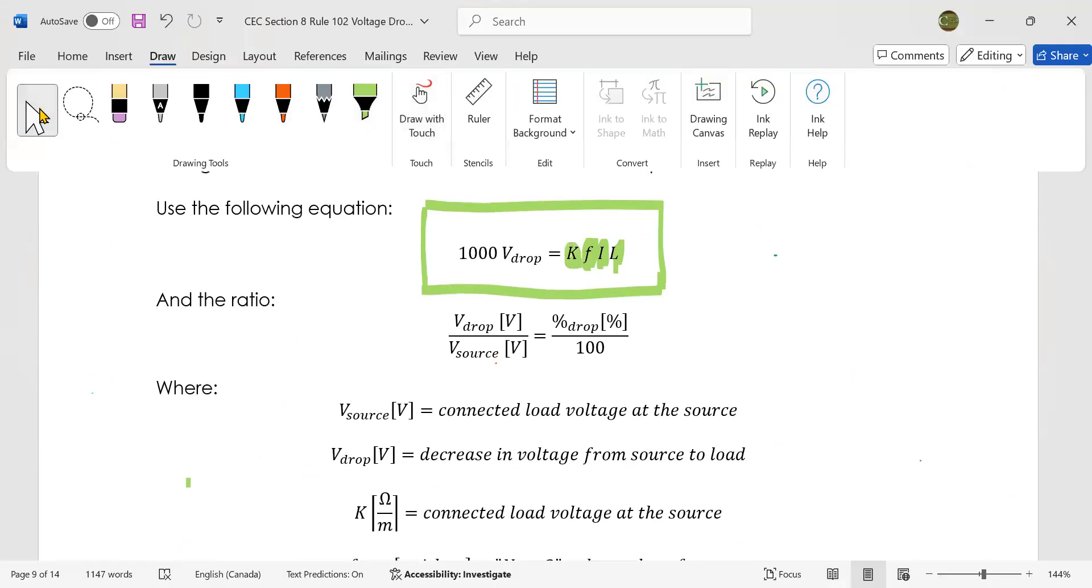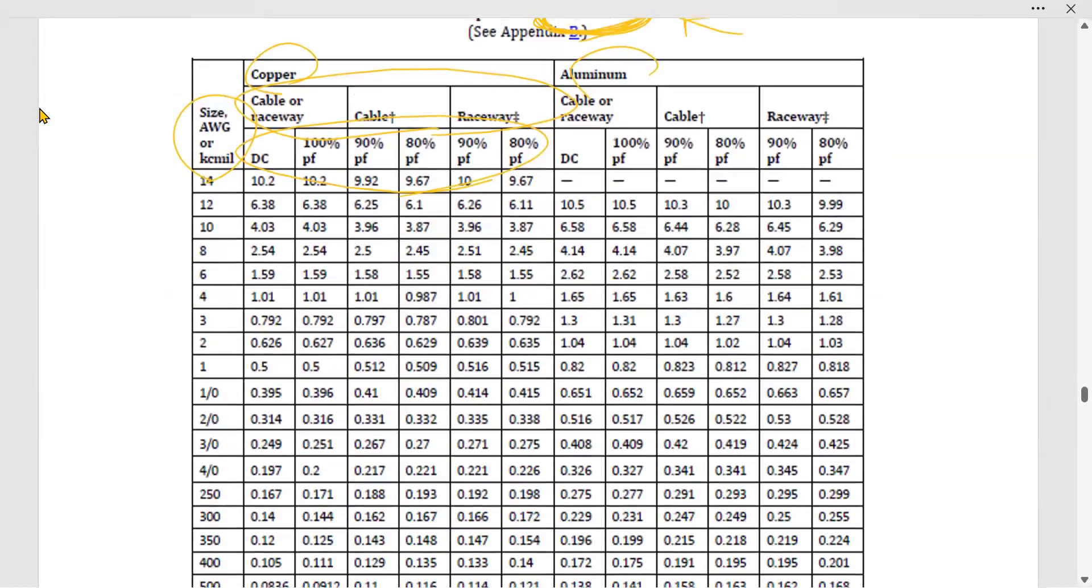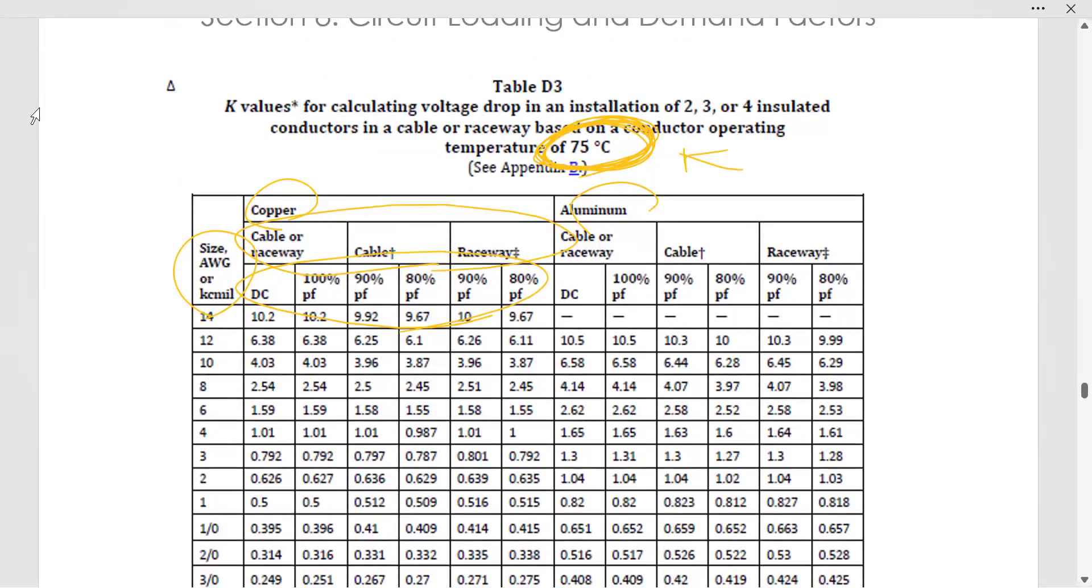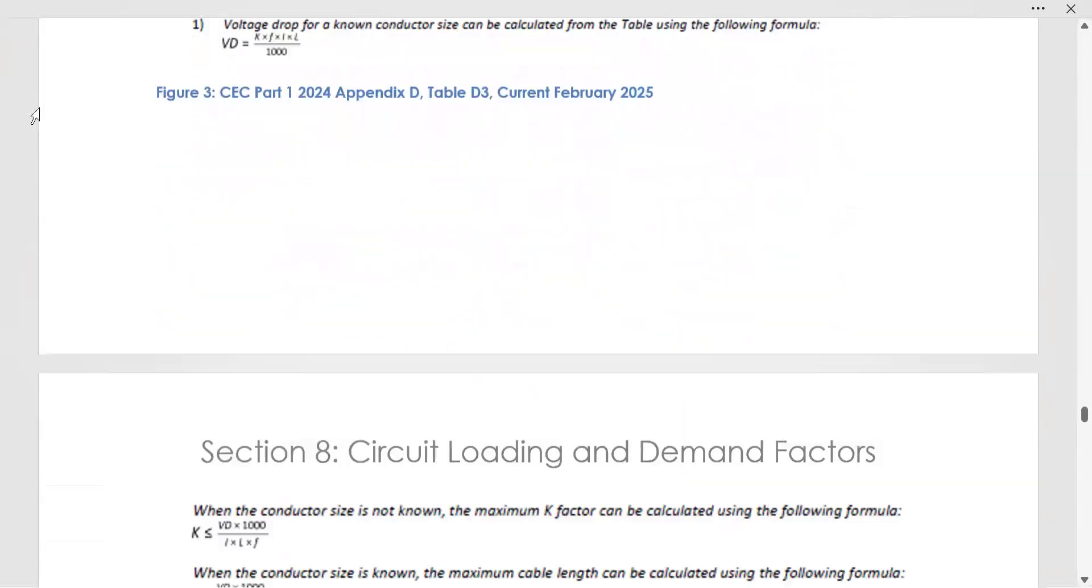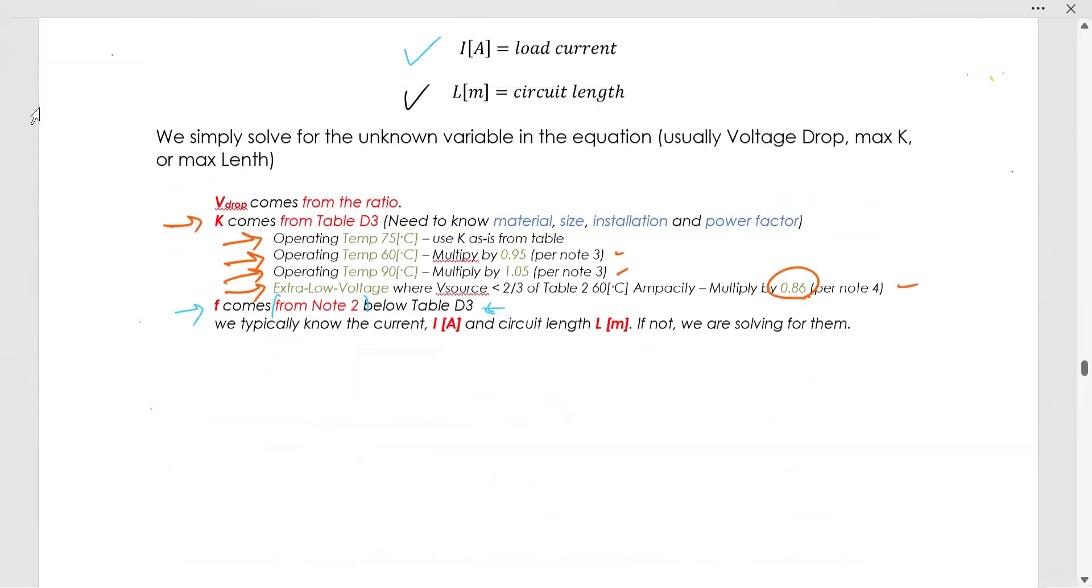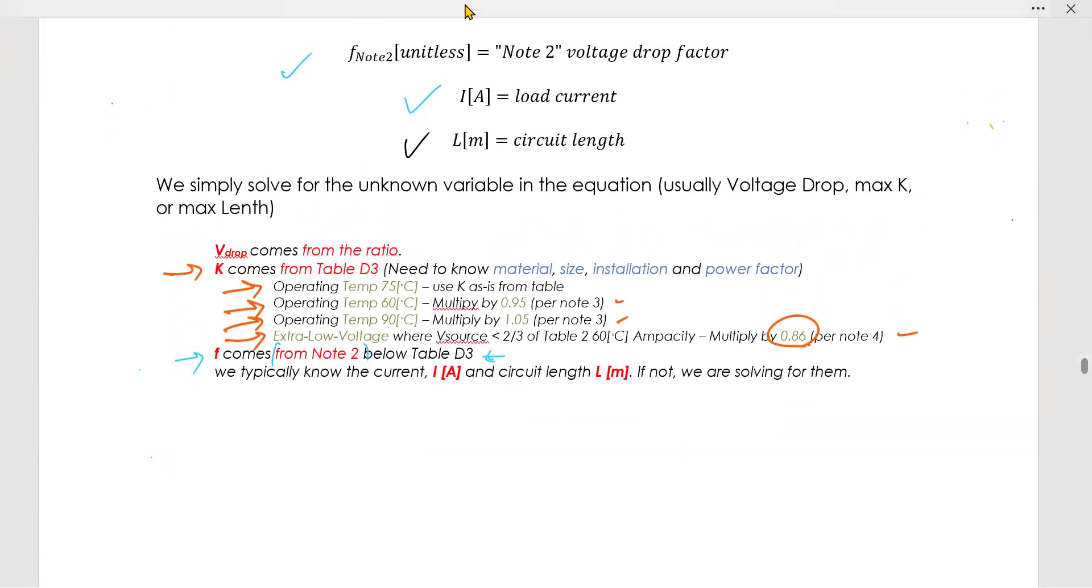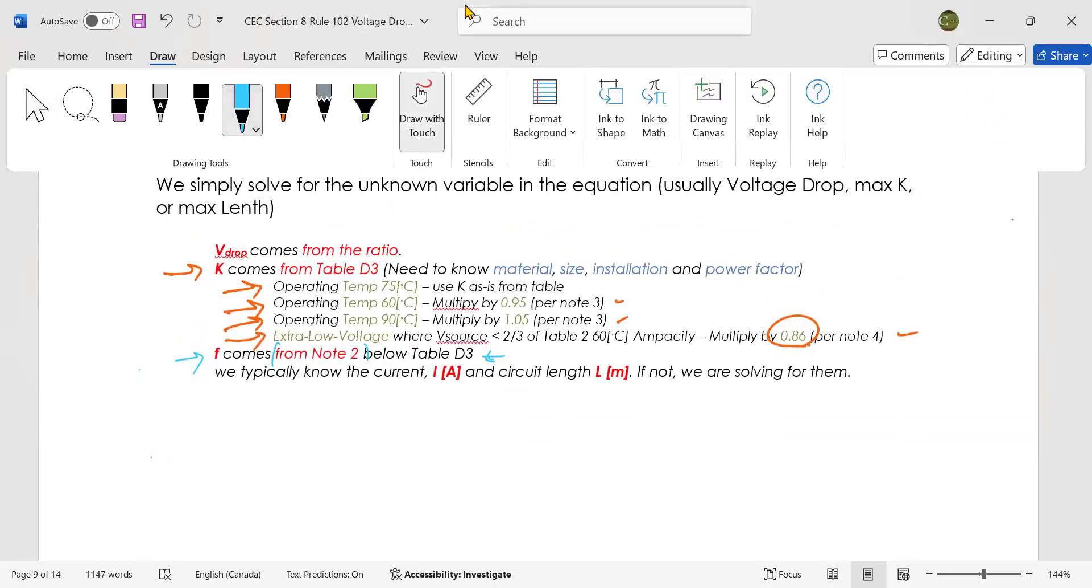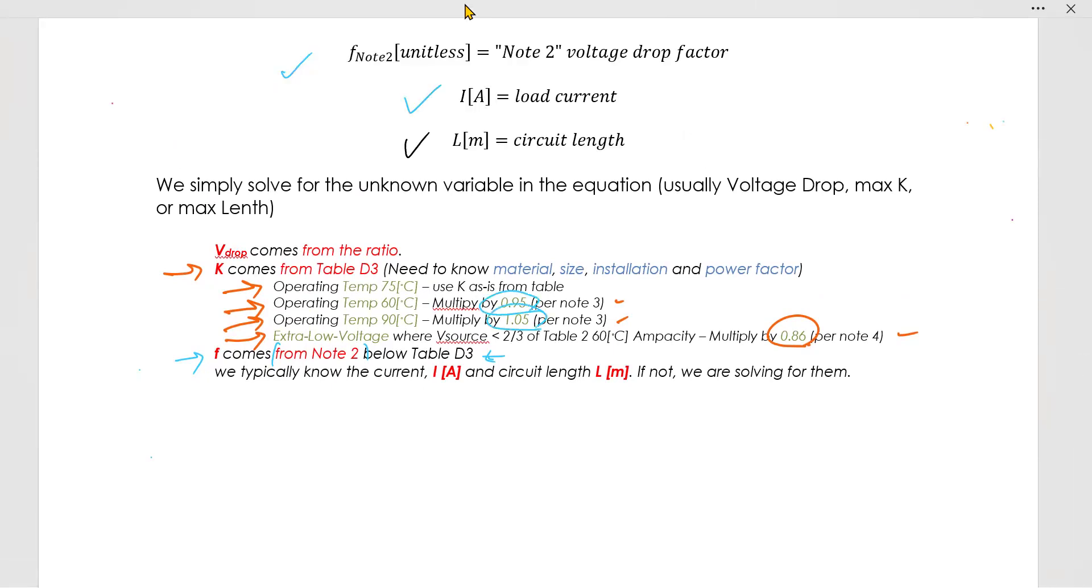F is either going to be 2 or 1.73 depending on the type of system you are calculating. K is a factor that comes from a table. The table looks like this. The table is set at 75 degrees, so you can use these values if you're at 75 degrees. If you're not at 75 degrees, then you are going to multiply that K value by 0.95 or 1.05 or 0.86.